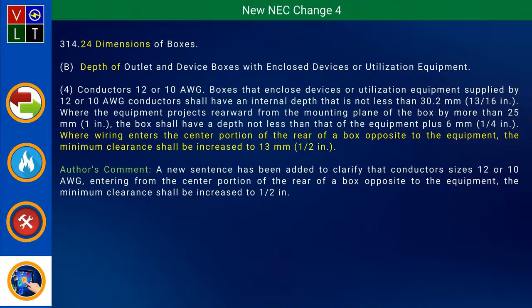They wanted to clarify that where you have conductor sizes that are number 12 or 10, entering from the center portion of the rear of the box, which would be opposite to the equipment you're going to install there, you have to have a minimum clearance that'll be increased to a half inch.